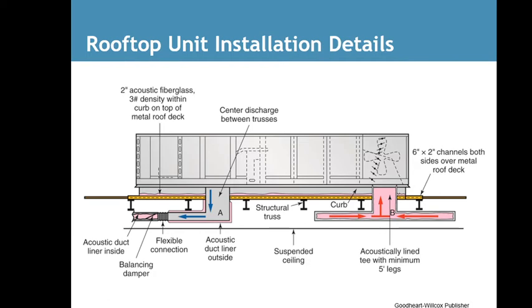Here are some requirements for rooftop unit installation. You can read over these. They're a lot easier to see in your book, like the distance from the curb to the ductwork, how it is measured, things like that. There are flexible connections on the supply on the bottom left-hand side. If you don't have them, you get a lot of vibration from the bigger units. So you need some of these things built onto this.